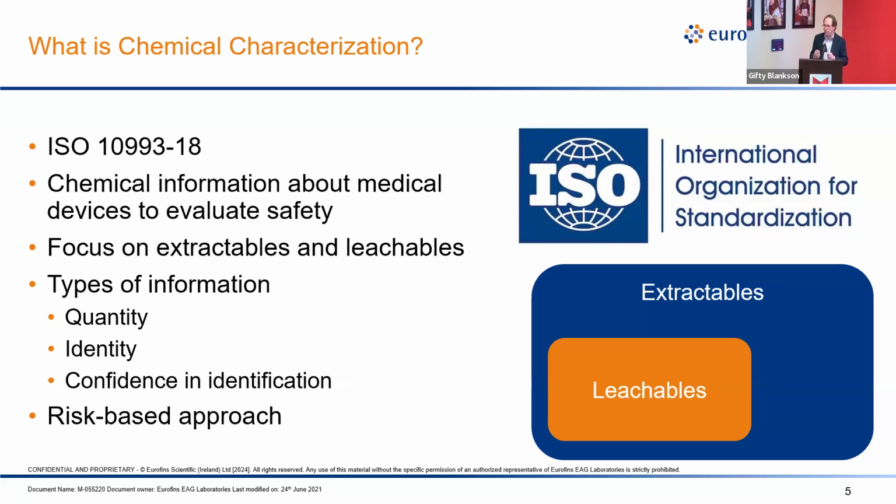And so we extract our device under those conditions, right? We'll do it in saline and we'll do it at 37 degrees Celsius. We'll look and we'll see what we see in it, if there is anything, what it is, that kind of stuff, right? This information is down below. But we want a little bigger margin of safety.